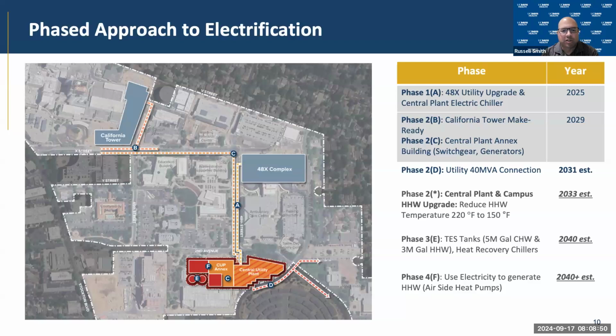Phase 2 is broken into several sections. The first section is more underground infrastructure for the new California Tower, which is a 14-story hospital bed tower, and a central plant annex building that will house new electrical switchgear and new emergency diesel generators. After that, we go into the phase of a new utility connection. With the added electrical loads that the campus will have, we need a new 40 MVA connection to our local utility. Additionally, there's one more step before we can make a big shift towards electrification, and that's reducing our current heating hot water temperature so that it'll work with new electrification technologies.